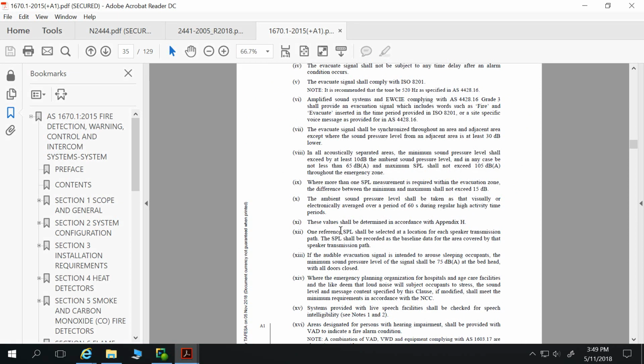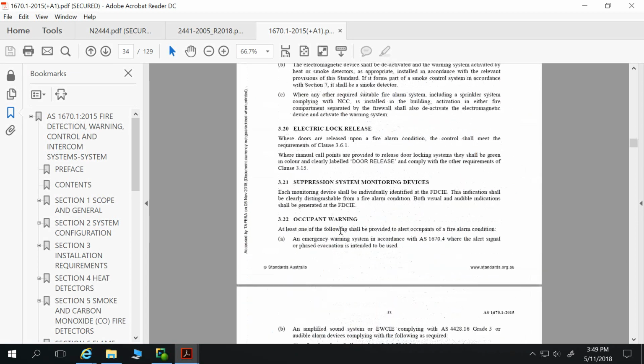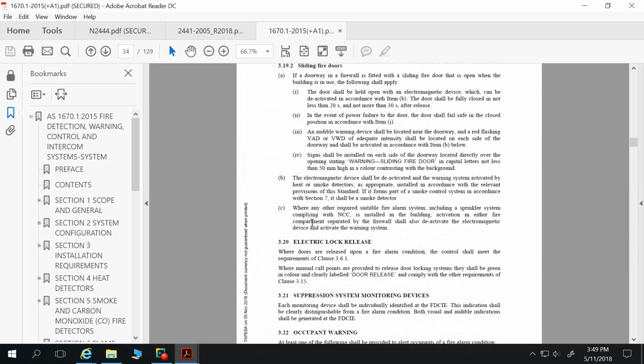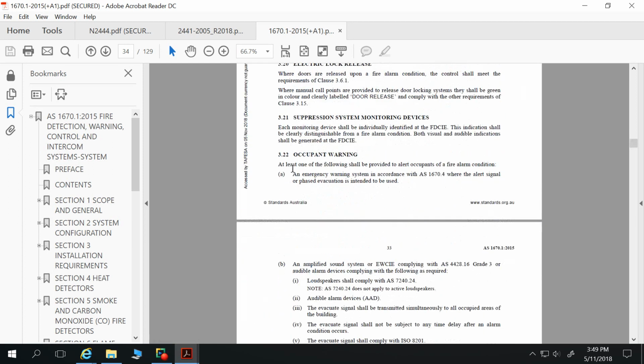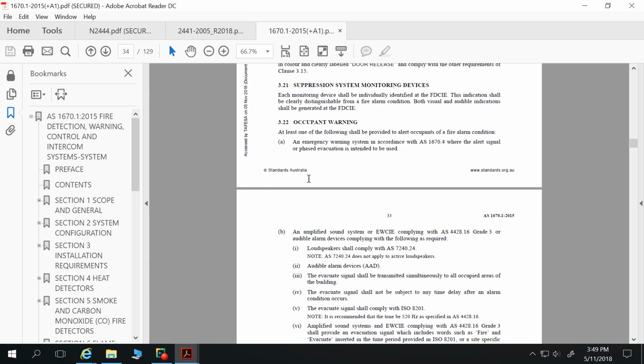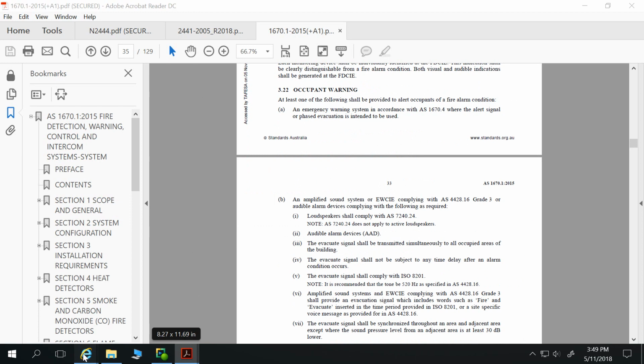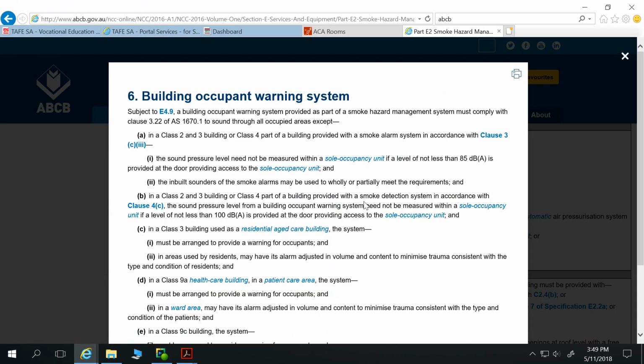So basically what it's saying is if we have a smoke detection system, it needs to work in concert with this alarm system, and that alarm system has to comply with that clause in terms of the occupant warning. So there are a few things in there that may be important for us to make notes of on our plans. Or you can just say an occupant warning system in accordance with 3.22. So back to the NCC for that one.